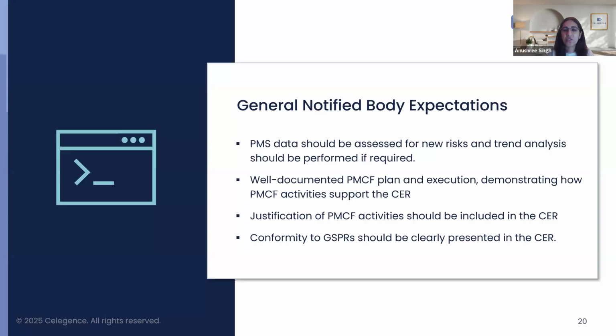In addition, a clear justification for the scope and design of PMCF activities must be included in the CER. Why certain PMCF methods were chosen, how they are appropriate for the device type and risk classification, and what are the expected outcomes when it comes to the benefit risk profile. The CER must clearly demonstrate also the conformity to the GSPRs outlined in Annex 1 of the EU MDR by identifying the applicable GSPRs based on the device's intended purpose and risk classification. This ensures that the technical documentation package is robust and audit ready. Right.